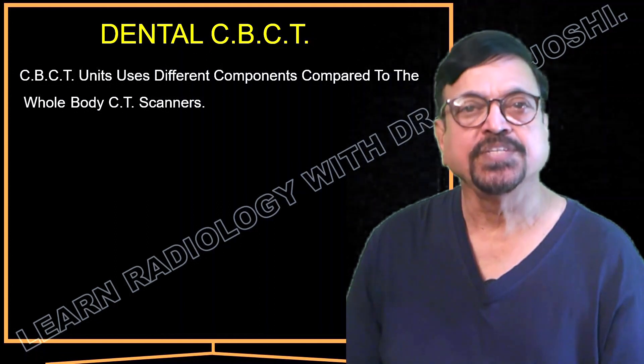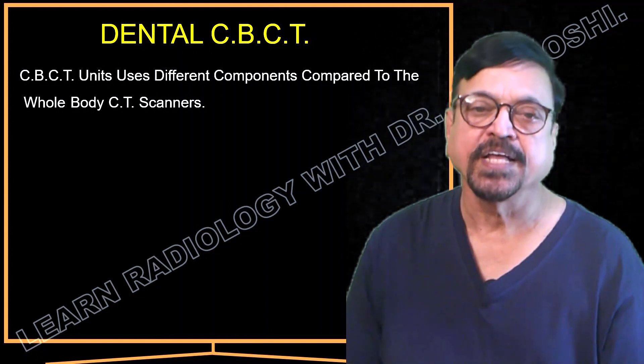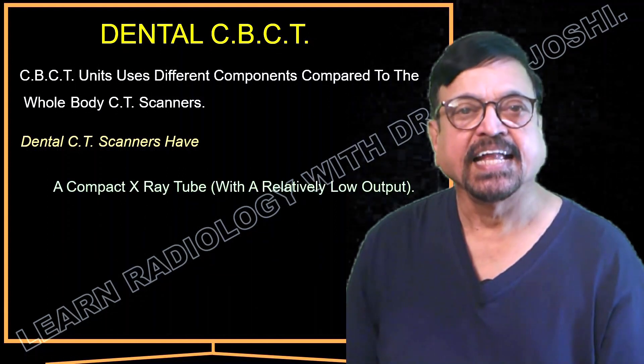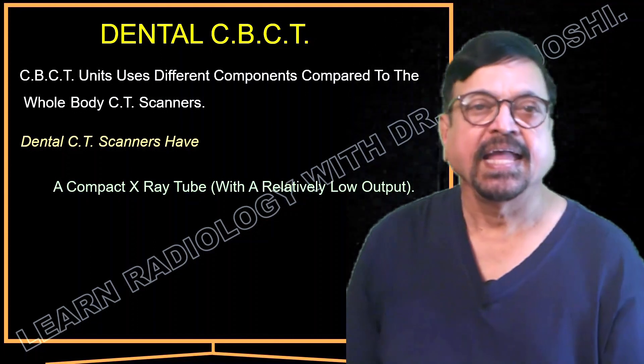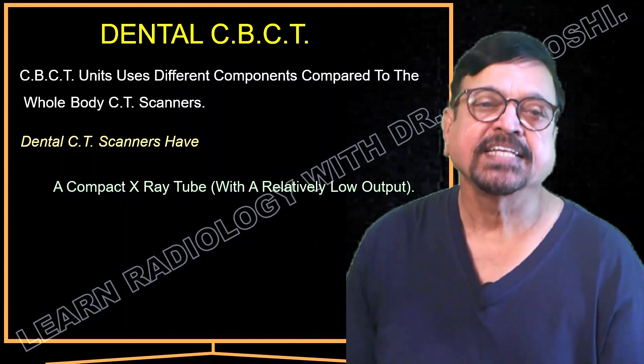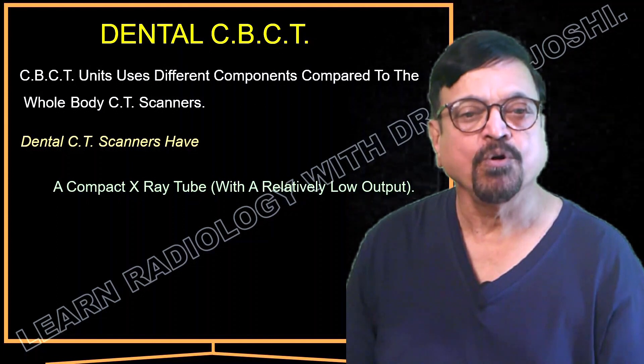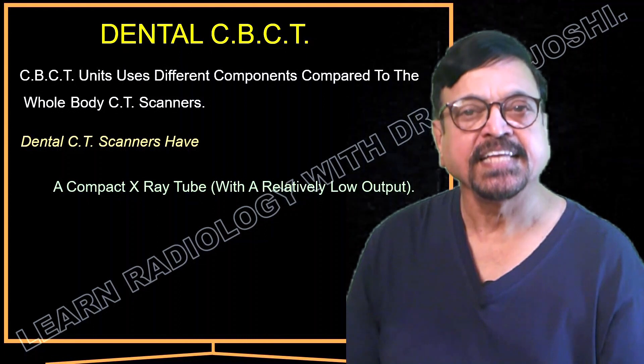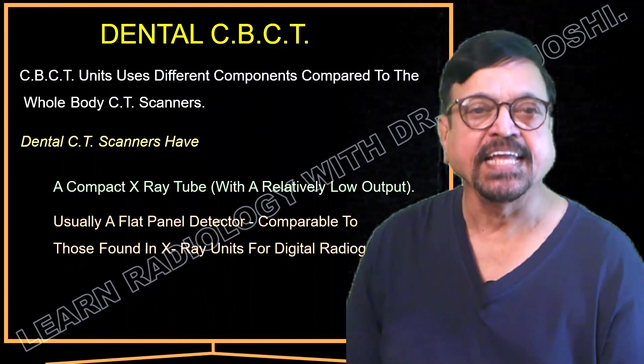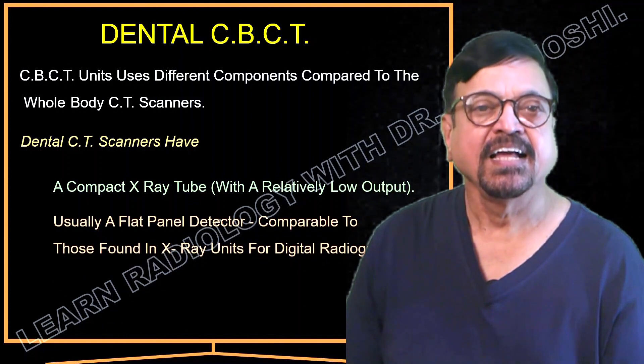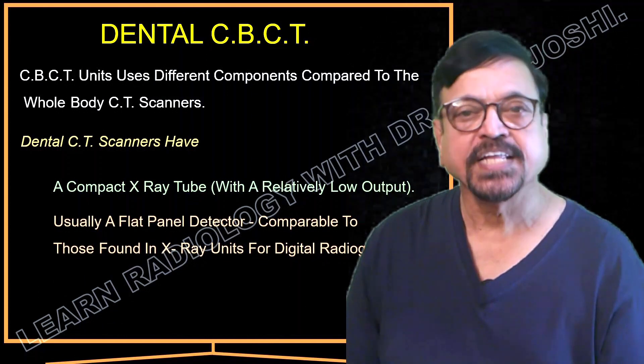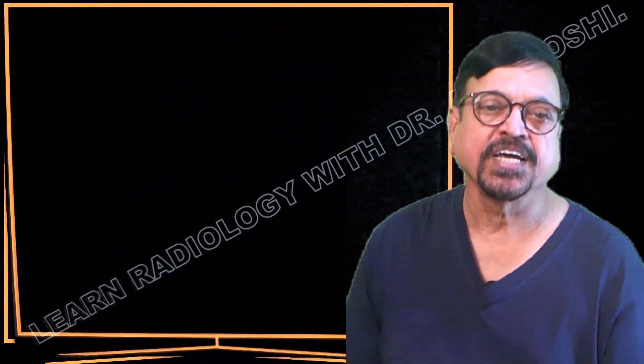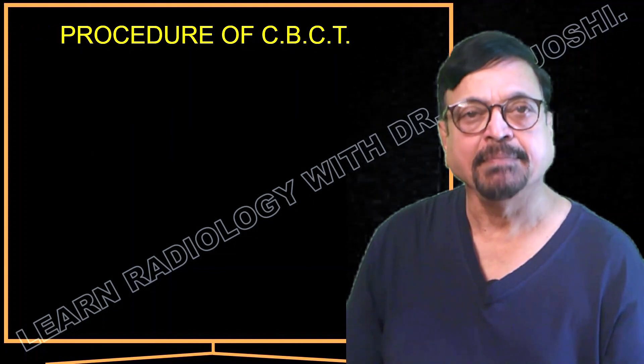CBCT units use different components compared to whole body CT scanners. Dental CT scanners have a compact X-ray tube — slightly larger than that of an OPG machine and smaller than a conventional CT machine — because it needs a relatively low output compared to conventional CT. A flat panel detector, similar to those used in digital radiography, is used here in a similar way to produce images.